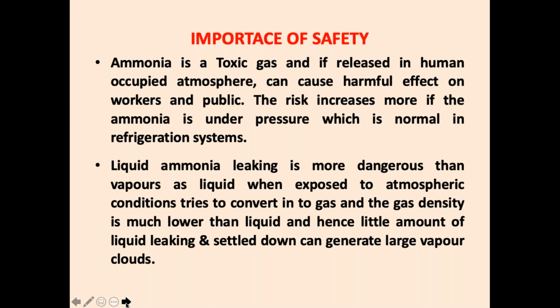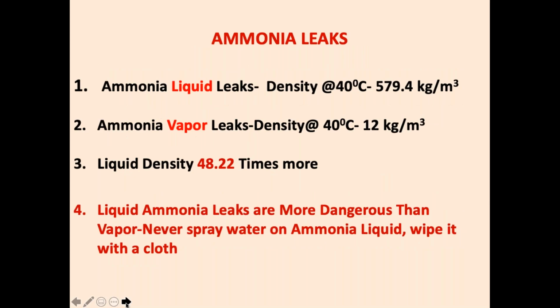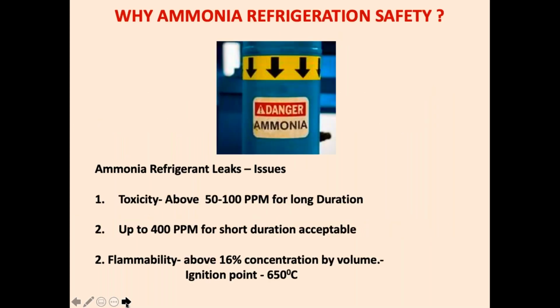My suggestion is never pour water on the liquid. Always wipe it out with a cloth after you take all other precautions like gloves, goggles, etc. But never spray water on the liquid. This is a very, very important suggestion. Just to give you an idea, look at this. Ammonia liquid density is very high, 500 odd. Ammonia vapor is only 12 kg per meter cube. So liquid density is 48.22 times more. So liquid ammonia leaks are more dangerous than vapor. Never spray water on ammonia liquid. Wipe it out with a cloth. This is an important suggestion which I am giving.